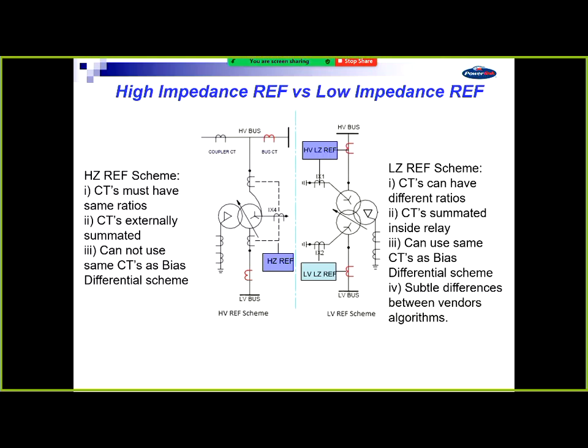On the right-hand side, you've got an HV REF scheme and an LV REF scheme. So they need to be in separate windings or separate elements in the same relay. A low impedance scheme, which is the one on the right-hand side, uses the same CTs as the high impedance, but that would be inside the bias differential relay that we've got. The thing you've got to watch when you're using those schemes inside a protection relay is that different manufacturers will use different algorithms to do it.